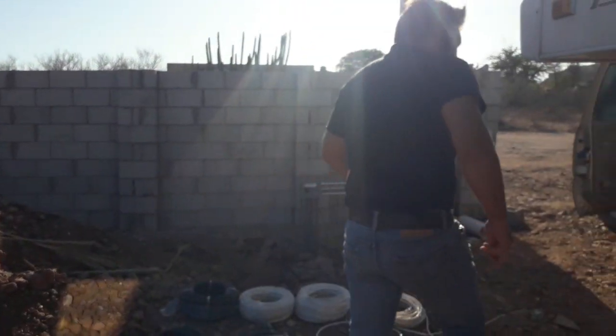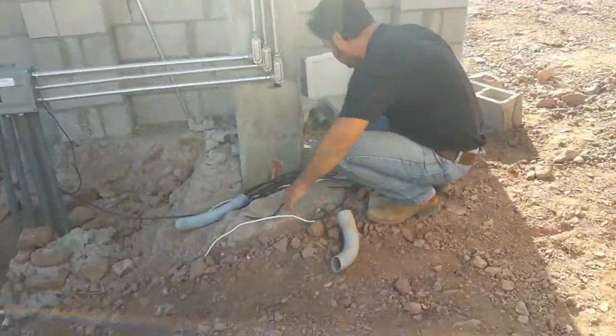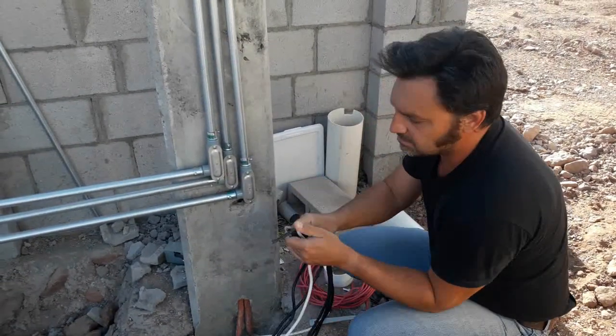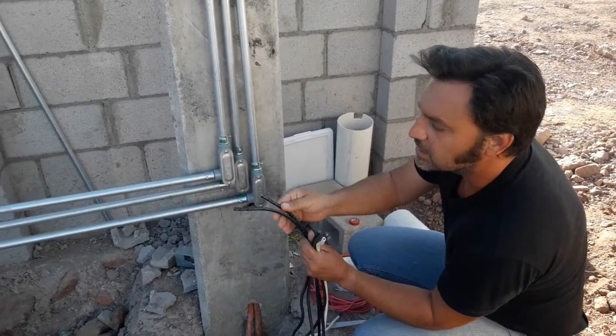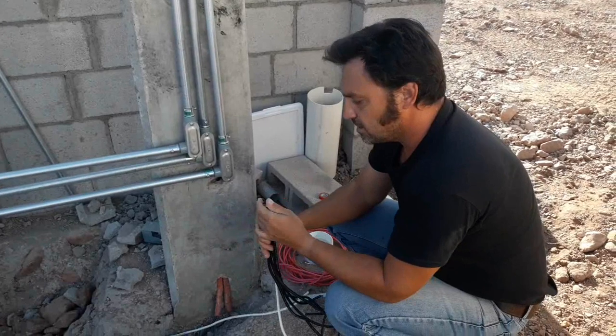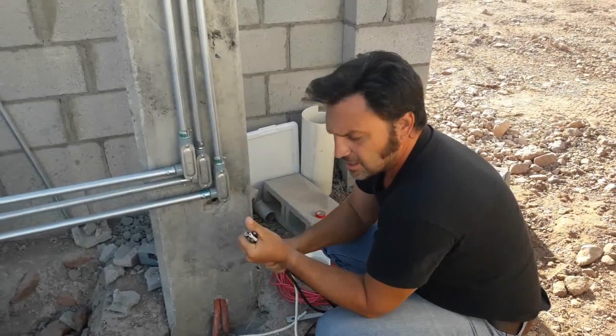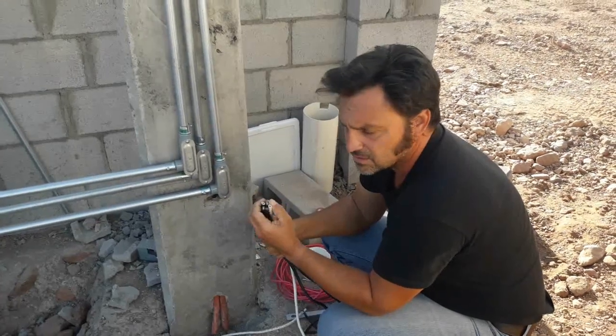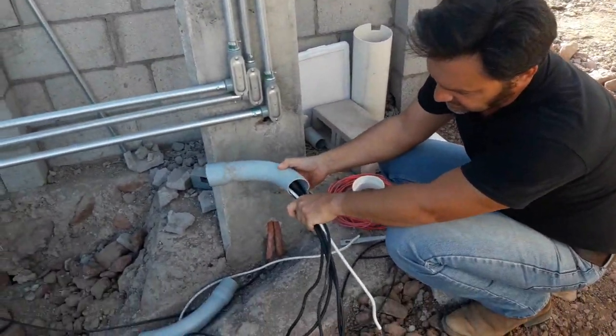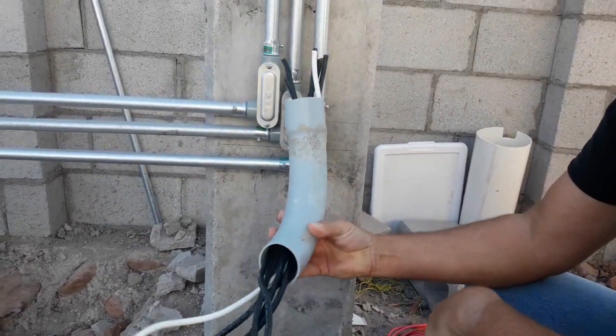The reason I went for the 2-inch conduit is, look, this is a 2-inch, just a piece. If you see, 1, 2, 3, 4, 5, 6, that many cables gonna go into it. But according to my research, you can actually have 40% in the pipes. You can take off 40%, because they might heat up, and it's also easy to pull it. Look, this is not even 40%, you see? It's like maybe 20. So they're gonna fit easily, you see? That many.